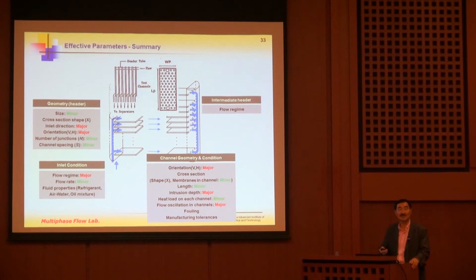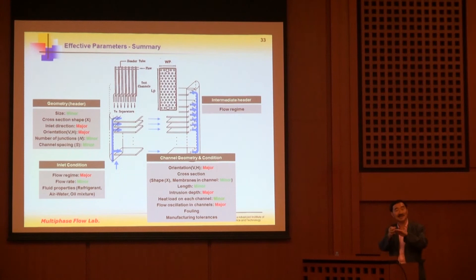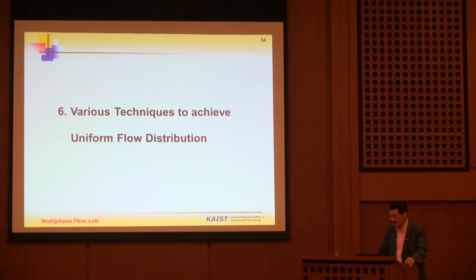For channel geometry, channel orientation (vertical or horizontal) is important, and the intrusion depth of the channel into the header also makes flow distribution very different. You may also have flow oscillations in the channel, which must be prevented. Flow regime problems in the intermediate header also need consideration. This is quite a difficult problem — in industry (for example, at LG Electronics), achieving uniform flow distribution is more art than pure engineering.